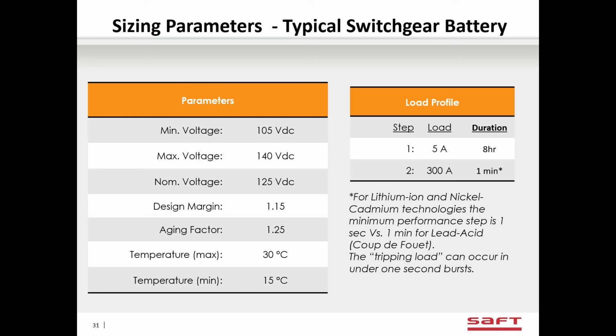Like I said, I prefer to put lithium-ion batteries in a temperature controlled space so that I know they're always going to be at a particular temperature. Usually we shoot for 25 degrees C. But if it's going to be uncontrolled, I need to know the min and the max because that affects the discharge of the battery.